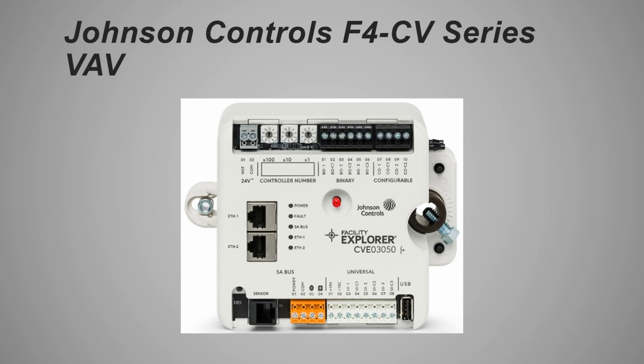They only make one size of the VAV controller now. Okay, this is the size. The numbers actually mean stuff now. So you take the first numbers, 0, 3, and that's how many inputs you have. Right here, we have UI1, UI2, UI3. So 3 inputs, right? The last numbers, 0, 5, is the total number of outputs you have. BO1 through BO3 is 3, and CO1 and CO2 make 5. A total of 5 outputs. Okay?